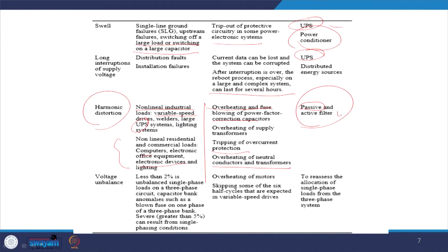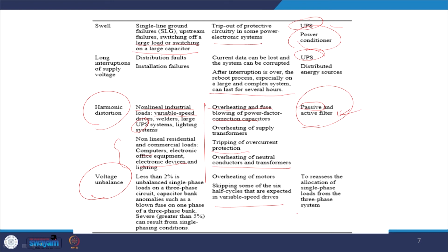Similarly, voltage unbalance: less than 2% unbalance is allowed for single phase loads on 3 phase circuits. Capacitor bank anomalies such as a blown fuse on one of the phases, or any other reason, may cause load unbalance. So, ultimately if there is an unbalance of more than 2%, then there will be overheating of the motor, skipping of some of the 6 cycles that are expected from the variable speed drive, and thus the torque rating of the motor will be reduced. To remove it we require a UPQC to reassess the allocation of single phase load from the 3 phase system.